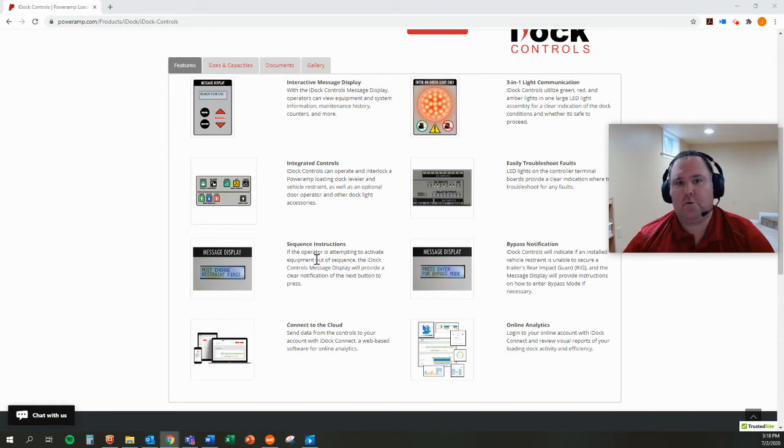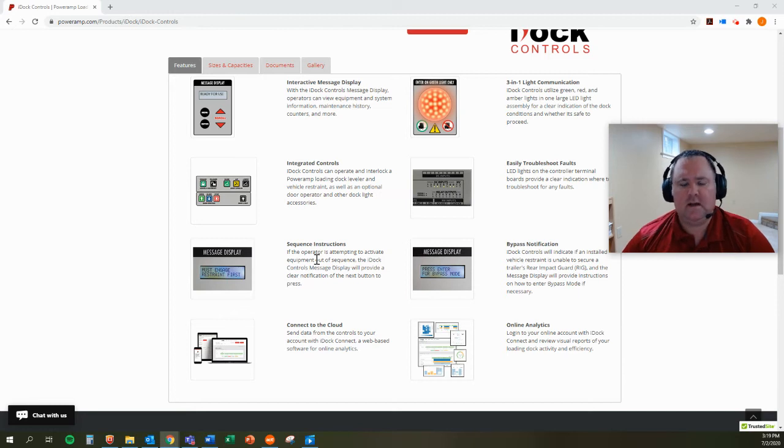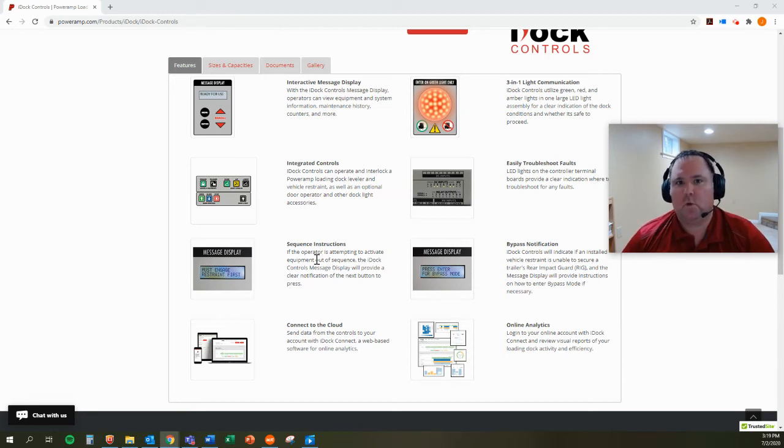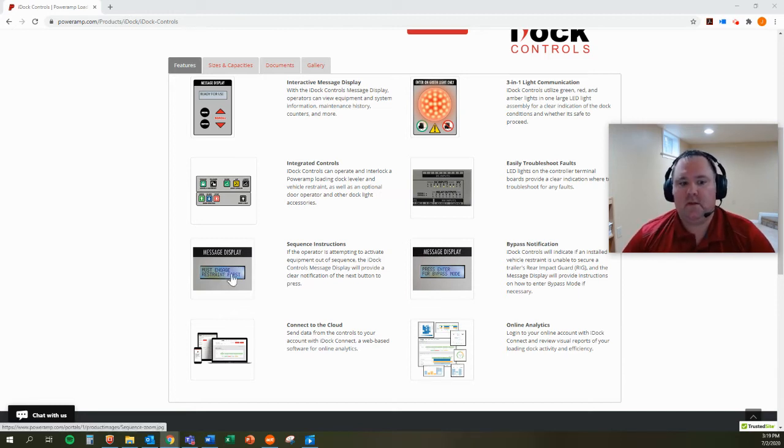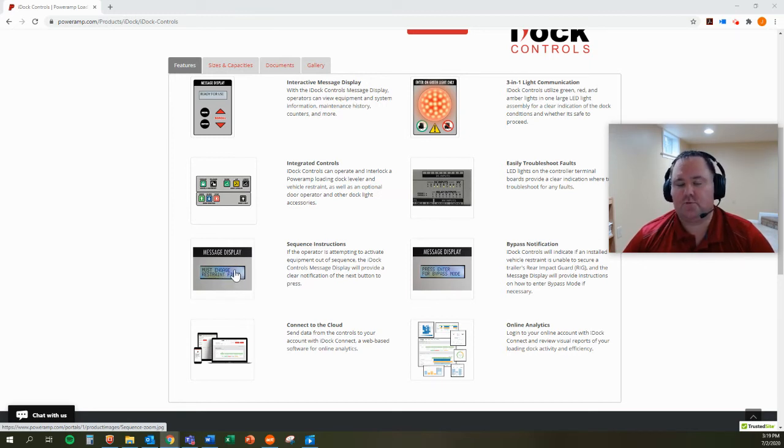So for example, if the dock operator opens the door and then tries to deploy the leveler, it's not working. He doesn't have to wonder what's going on or what he needs to do. It actually tells the dock operator on the controller screen, the message display actually says must engage restraint first. So it's a smart controller.